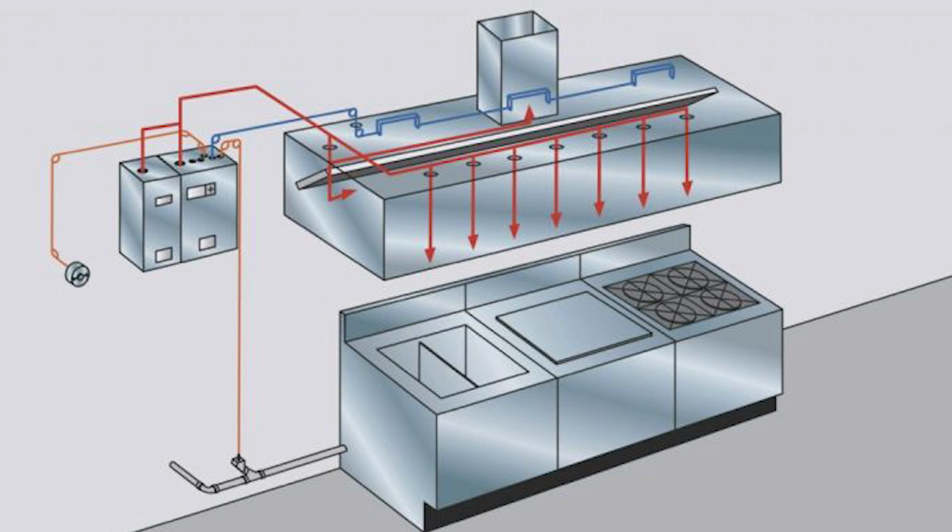I just saw one recently, full-blown Ansul system. This was a 40-inch grill head. It had a 9-foot, very expensive, customized Ansul system, approved by the manufacturer. It was a steel structure. This was a very expensive, well-done room. Shut down. Absolutely shut down. Rip it all out. Because that inspector interpreted it the way he did. And that's their right too.